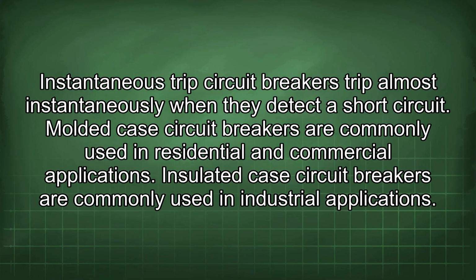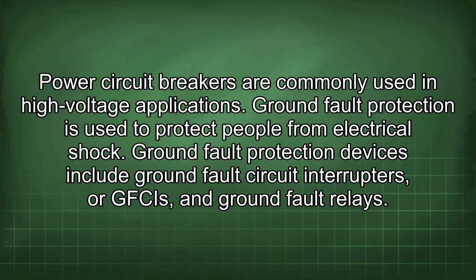Molded case circuit breakers are commonly used in residential and commercial applications. Insulated case circuit breakers are commonly used in industrial applications. Power circuit breakers are commonly used in high voltage applications. Ground fault protection is used to protect people from electrical shock. Ground fault protection devices include ground fault circuit interrupters, or GFCIs, and ground fault relays.